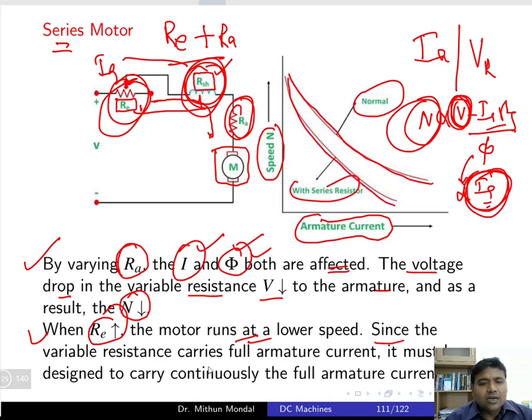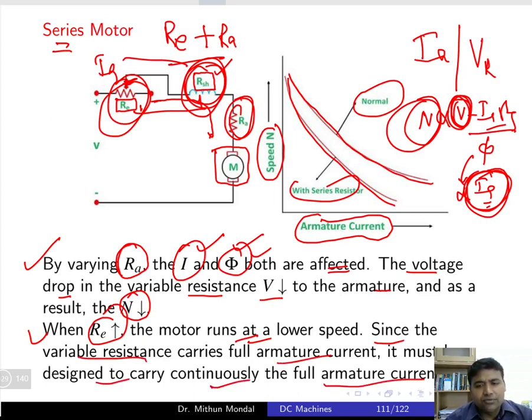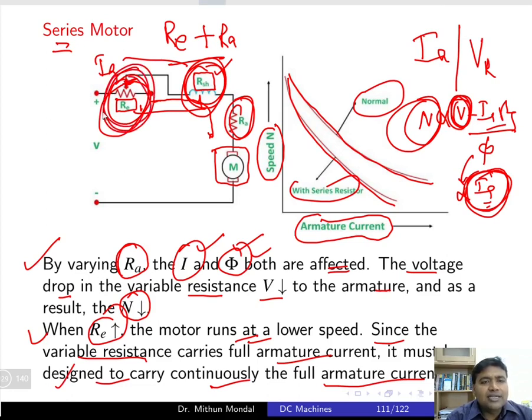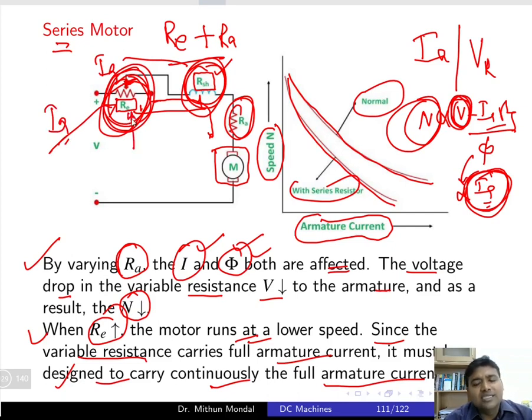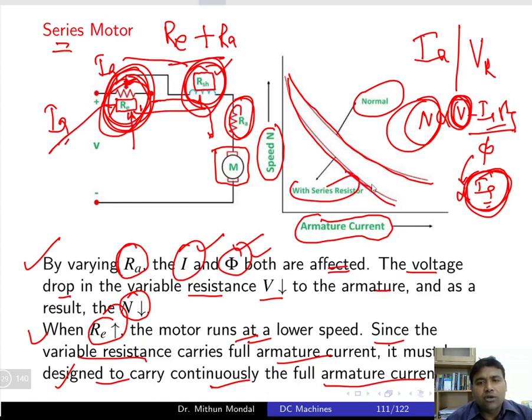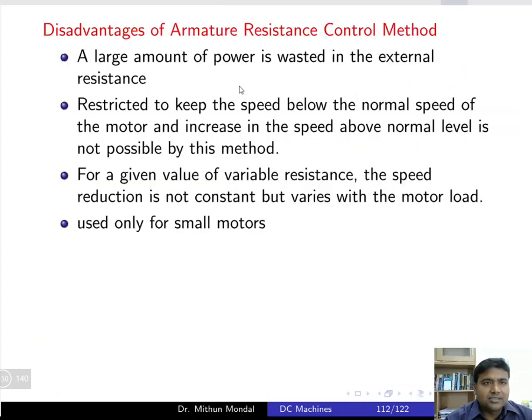Since the variable resistance carries the full armature current, it must be designed to carry the full armature current continuously. The rheostat must be properly designed to bear the maximum full-load armature current. In this method, the speed falls by controlling the armature resistance.